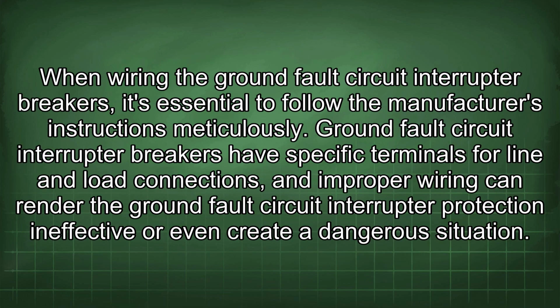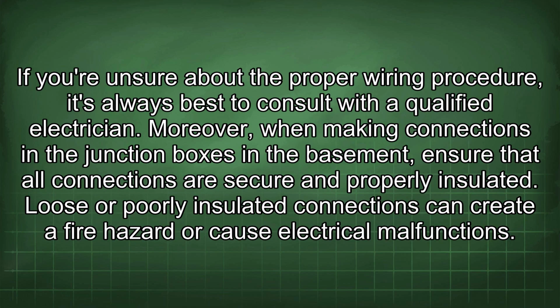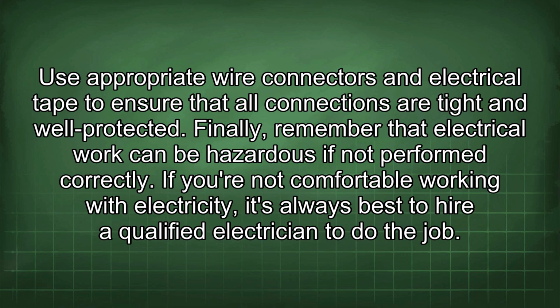When wiring the ground fault circuit interrupter breakers, it's essential to follow the manufacturer's instructions meticulously. Ground fault circuit interrupter breakers have specific terminals for line and load connections, and improper wiring can render the ground fault circuit interrupter protection ineffective or even create a dangerous situation. If you're unsure about the proper wiring procedure, it's always best to consult with a qualified electrician. Moreover, when making connections in the junction boxes in the basement, ensure that all connections are secure and properly insulated. Loose or poorly insulated connections can create a fire hazard or cause electrical malfunctions. Use appropriate wire connectors and electrical tape to ensure that all connections are tight and well protected.